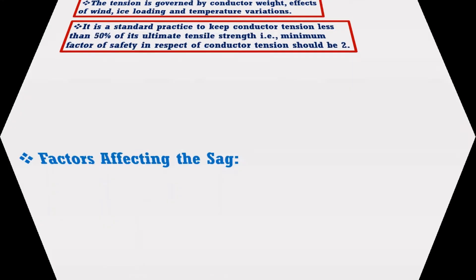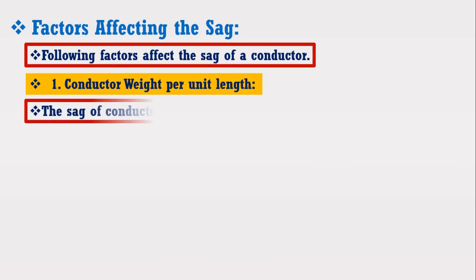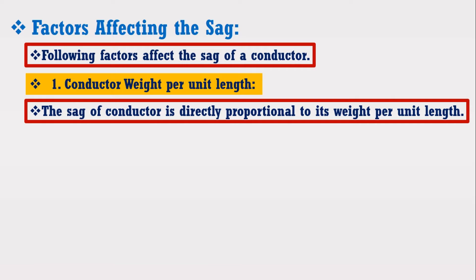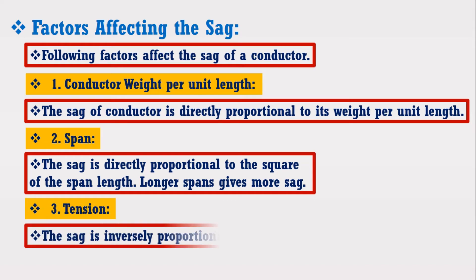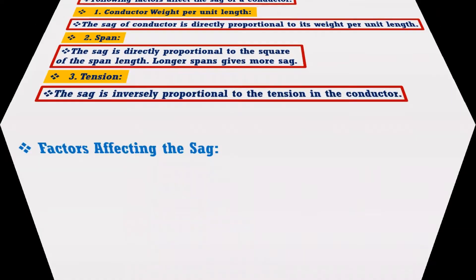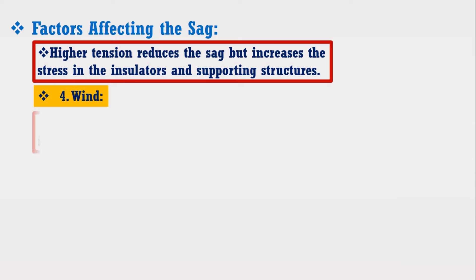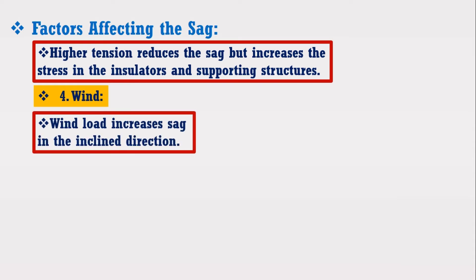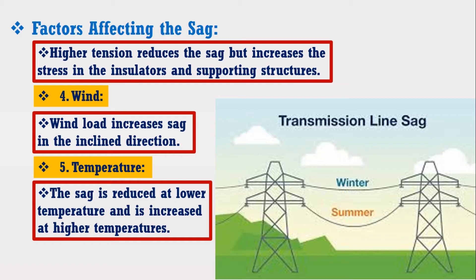Now I am going to discuss the factors affecting the sag. 1. Conductor weight per unit length: the sag of a conductor is directly proportional to its weight per unit length. 2. Span: the sag is directly proportional to the square of span length; longer span gives more sag. 3. Tension: the sag is inversely proportional to the tension in the conductor; higher tension reduces sag but increases stress in the insulators and supporting structures. 4. Wind: wind load increases the sag in the inclined direction. 5. Temperature: the sag is reduced at lower temperature and is increased at higher temperatures, as shown in the figure.